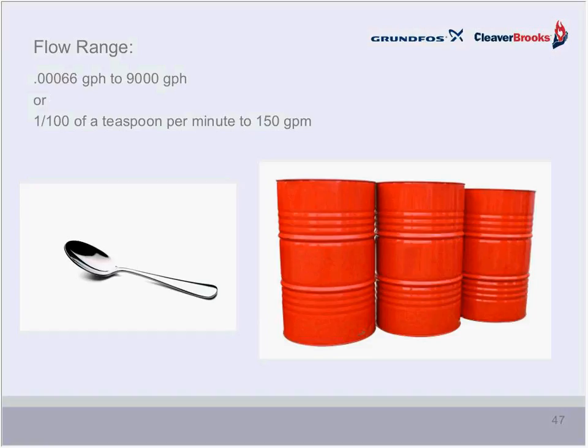This range can't be achieved by one pump in particular, but you see dosing pumps have a large range in the broad family. What this means today is that a wide variety of flows can be dosed with accuracy across a wide range of sizes of steam boilers.